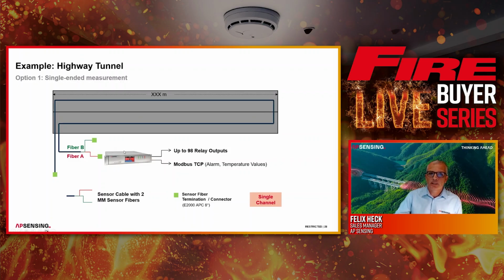So we have here, for example, a highway tunnel. This is the application we mainly have, and we want to protect this highway tunnel with a single-ended measurement. That means we have the controller in the control room, and one fiber connected to the controller, and we measure from the controller until the end of the sensor cable, and that's it. If there is an interruption, the rest of the sensor cable is not protected anymore, so this has to be considered. And this is a very simple measuring concept.